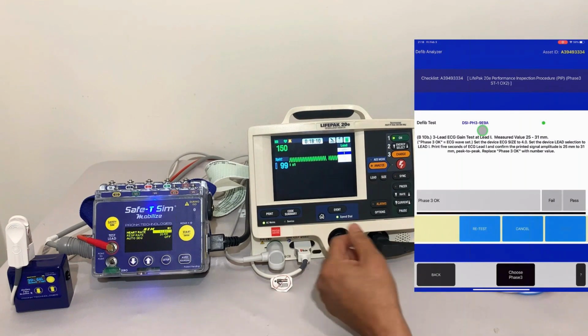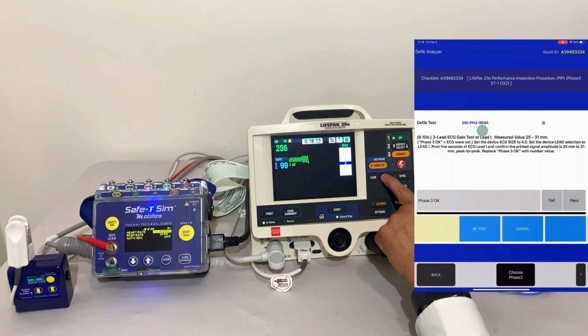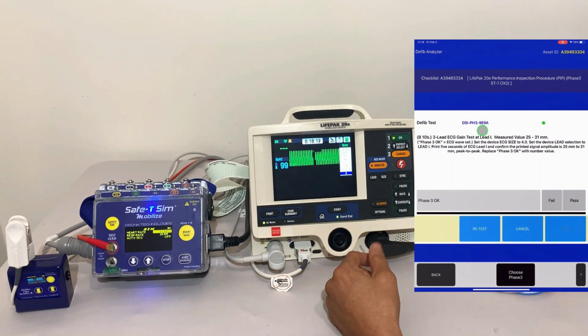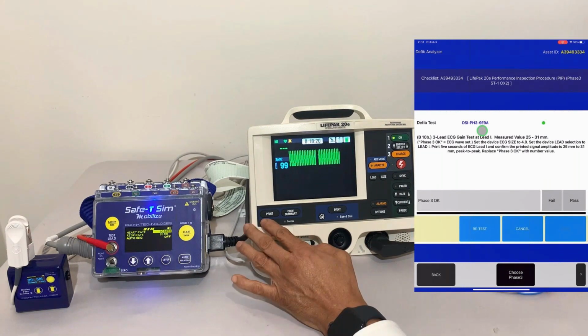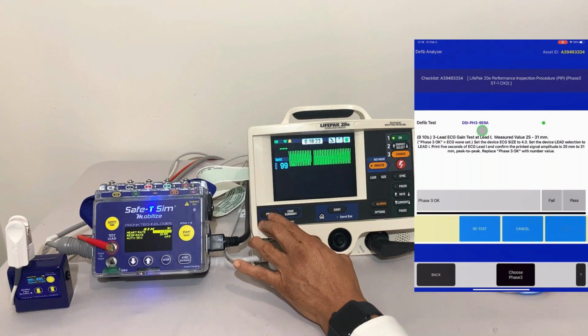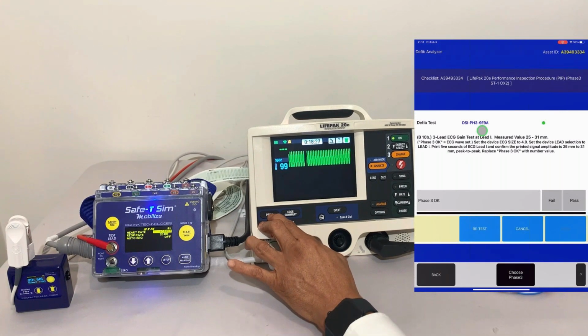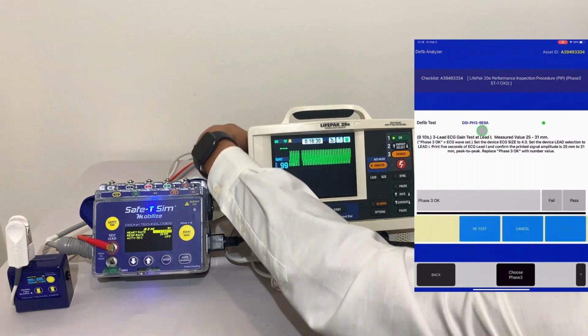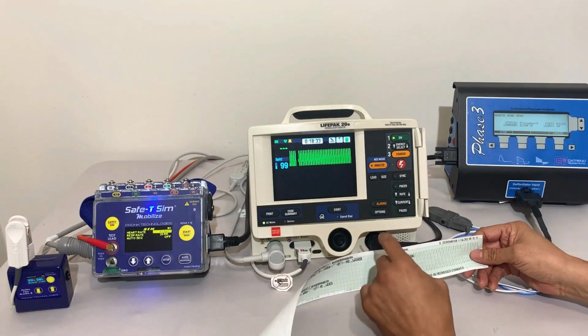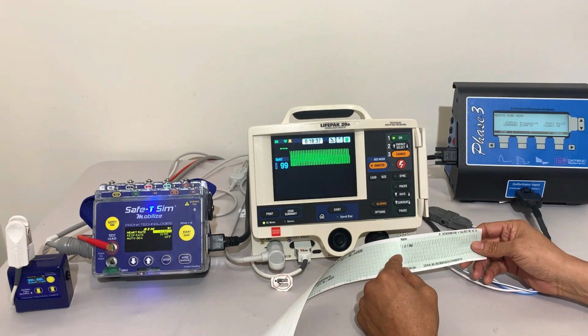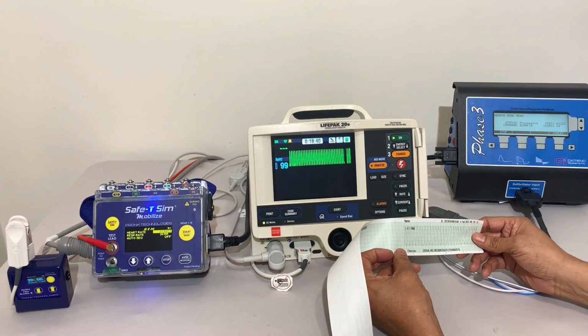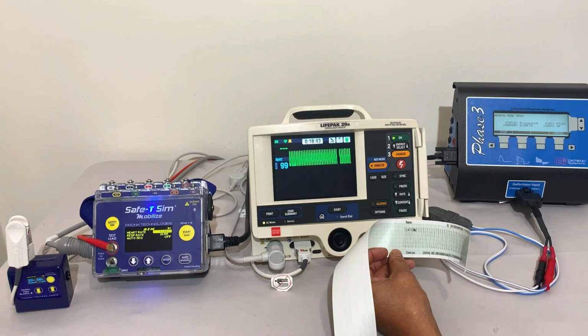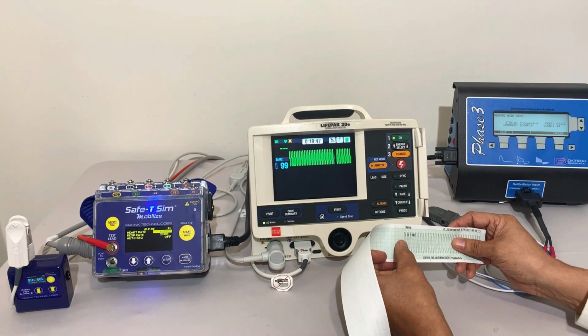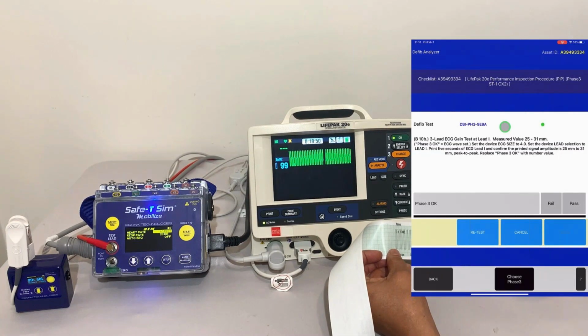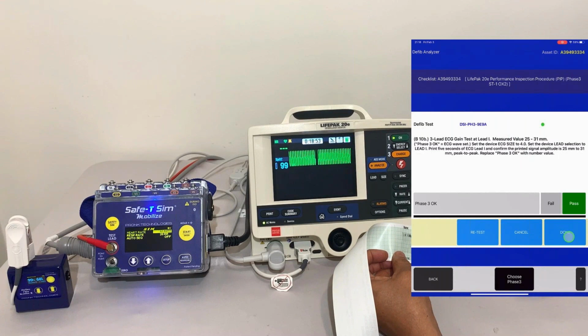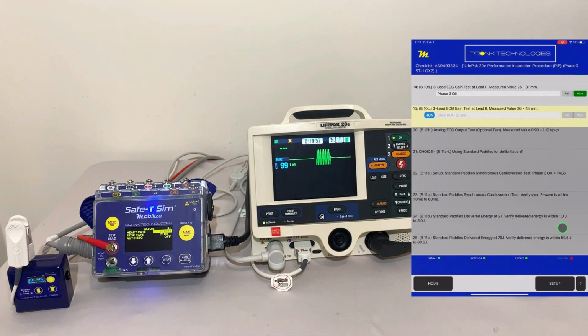We want to set the gain to ×4, so we're going to go ahead and do that. Then we're going to print out a strip and verify that the amplitude is within the range required. I'm going to print out a quick strip here so you can see it. I'm going to stop that printer and go ahead and get that. We can confirm by reading the strip recorder that this strip is measuring between 25 and 31 millimeters as required per the procedure. I can see here it's measuring about 27, so this is within range, this passes. I'm going to go through all of the required tests for the gain test to complete that.